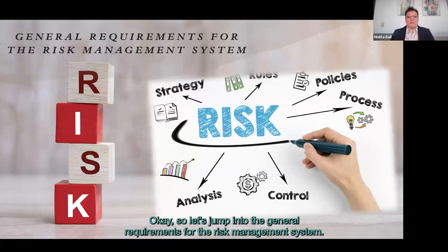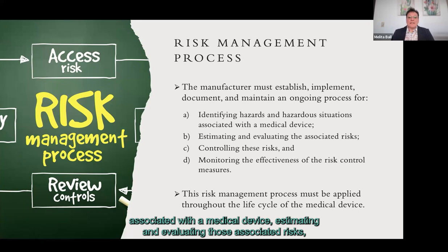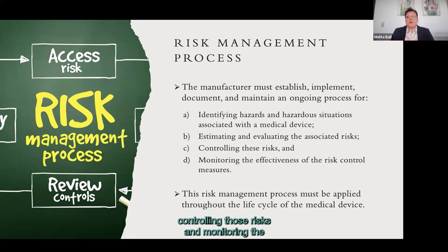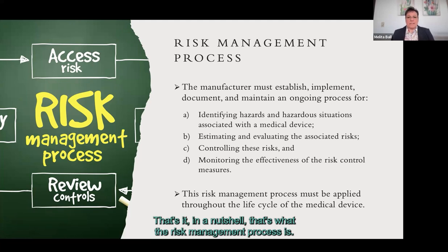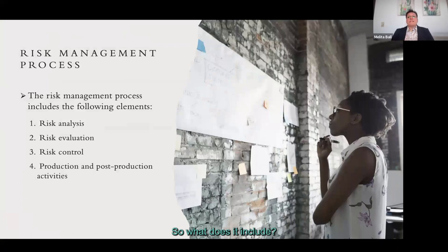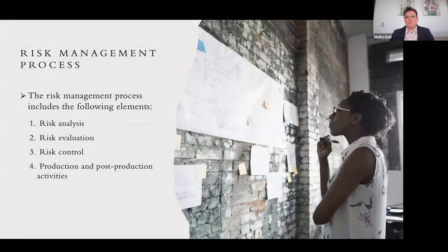Let's jump into the general requirements for the risk management system. Every manufacturer must establish, implement, document, and maintain an ongoing process for identifying hazards and hazardous situations associated with a medical device, estimating and evaluating those associated risks, controlling those risks, and monitoring the effectiveness of those risk control measures. This must be applied throughout the life cycle of the medical device, from the beginning of design through market withdrawal. It includes risk analysis, risk evaluation, risk control, and production and post-production activities.